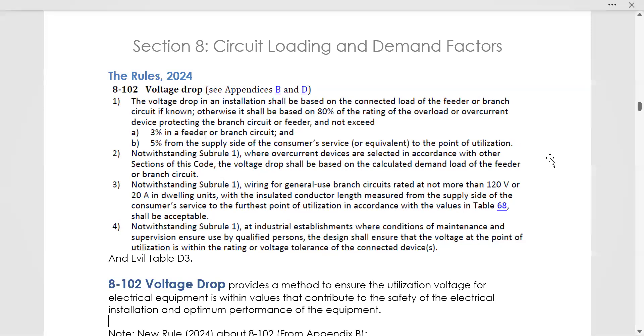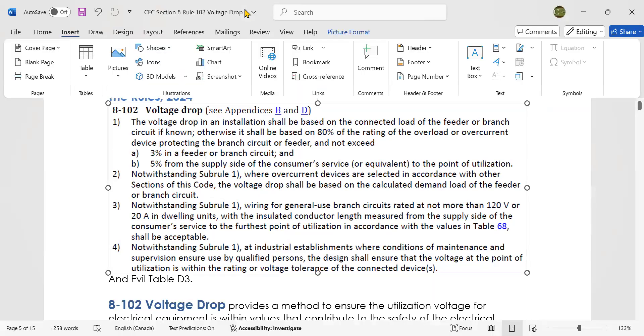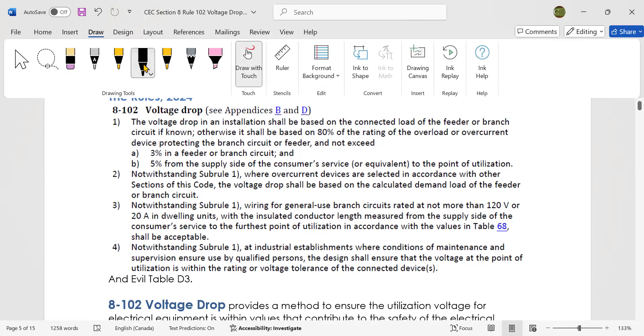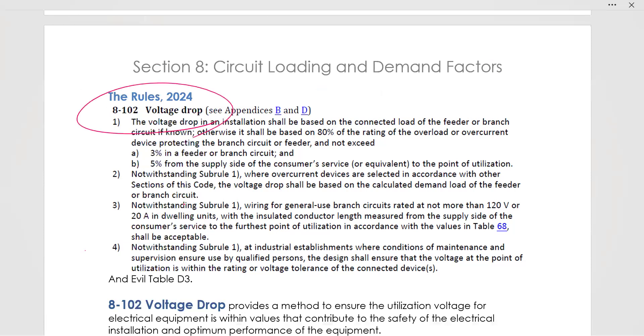Well, I'm going to take a moment to review the rule that is 8102 voltage drop. So let's look at what it says in the 2024 edition of the Canadian Electrical Code before we go ahead and do some example problems on a different video, because everybody's waiting for example problems. So voltage drop rule 8102, I do have another video that talks about why voltage drop is significant. This is a really important section, it provides a method to ensure the utilization of voltage for electrical equipment is within the values that contribute to the safety of the electrical installation and optimum performance of the equipment.